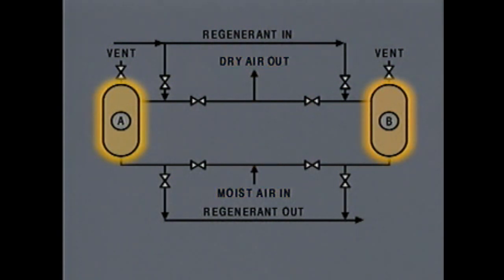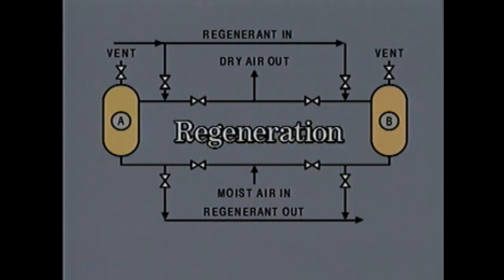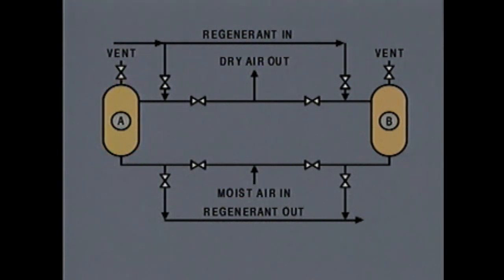The air dryer system takes in moist air from the atmosphere and provides an uninterrupted supply of dry air. Each dryer contains material called a drying agent that traps moisture as the air passes through the dryer. Periodically, the moisture is removed from the drying agent by a process called regeneration. Only one dryer is required to be in service at a time — while one dryer is in service, the drying agent in the other dryer is regenerated to remove trapped moisture.